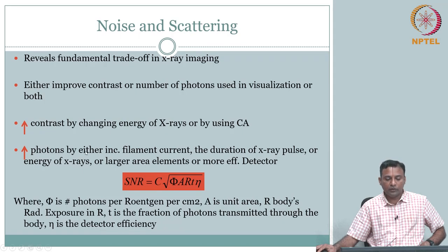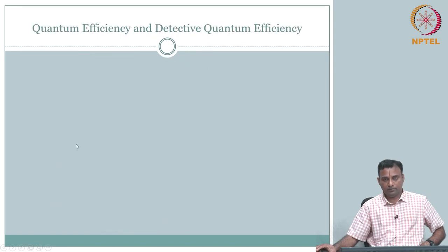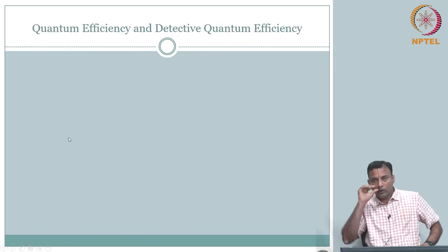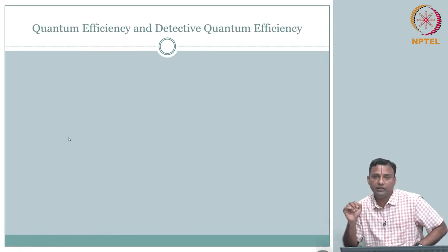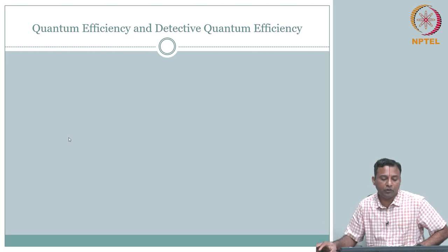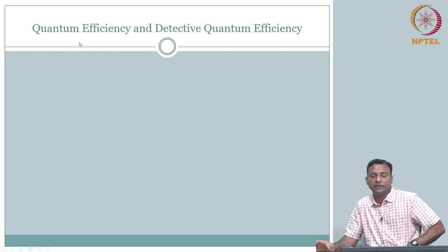If I can use a more efficient detector, I can definitely get better signal-to-noise ratio for all other parameters unchanged. We need to characterize detector efficiency — what do we mean by it and how do we improve it. The SNR is contrast times √N_B. N_B can be written in terms of contributing factors: φ is the number of photons per roentgen per cm², a is unit area, r is exposure, t is fraction of photons transmitted through the body, and η is detector efficiency. All these contribute to increasing N.